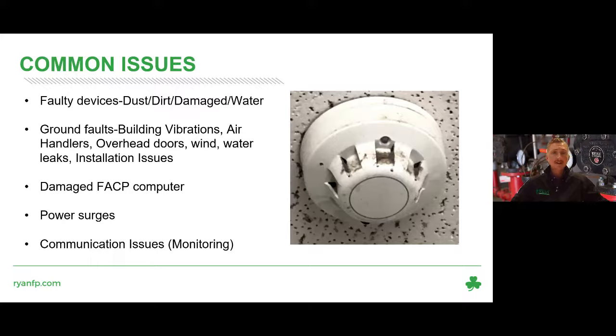Starting at the top, one of the most common things we see is faulty devices, smoke detectors, like the picture we show here. Sometimes they just get dirty, too much dust, depends on what type of environment they're in. They get damaged by forklifts or hit.